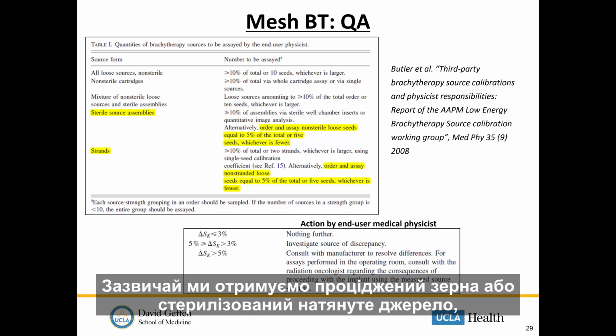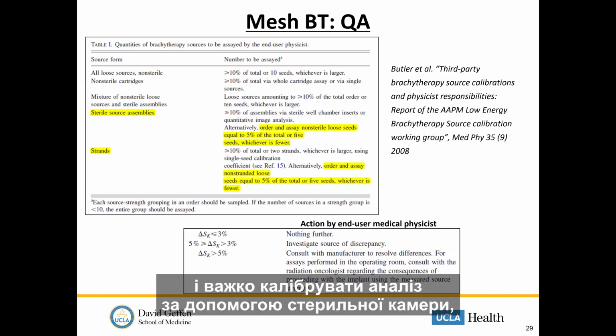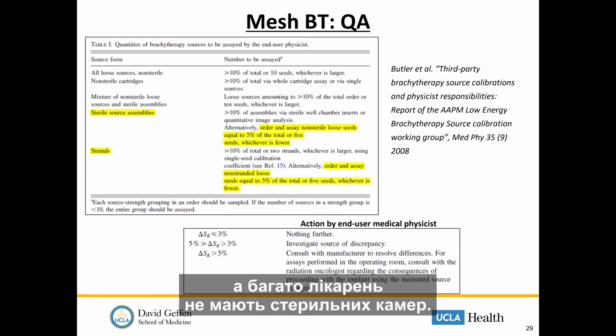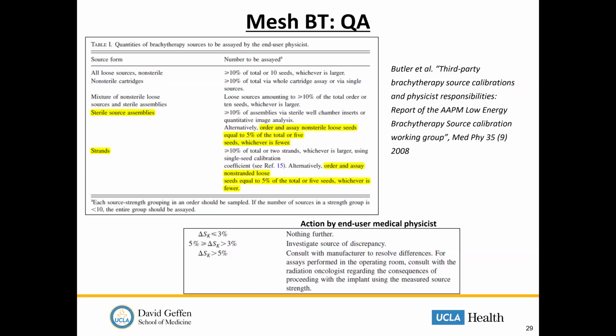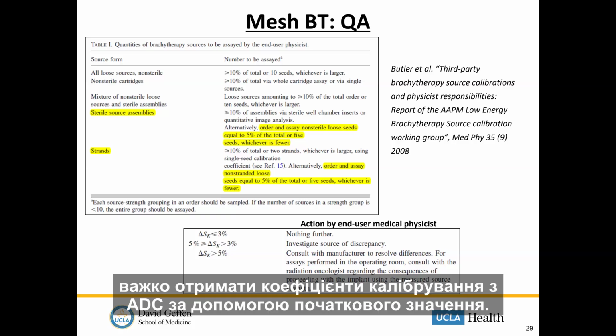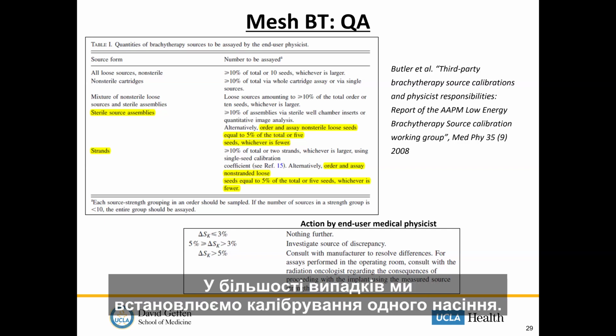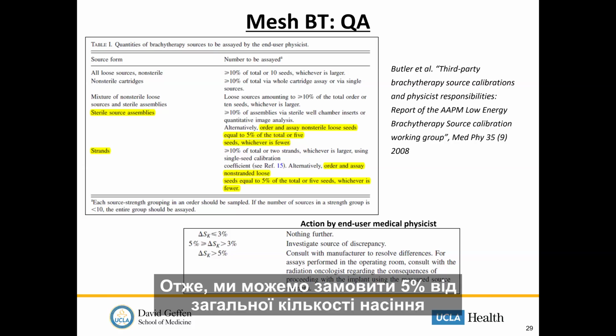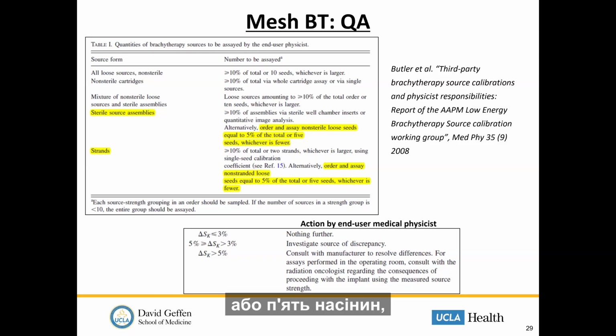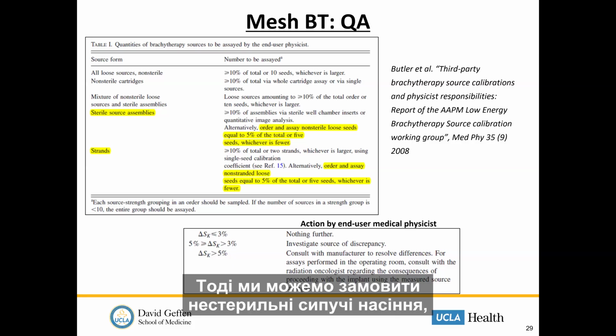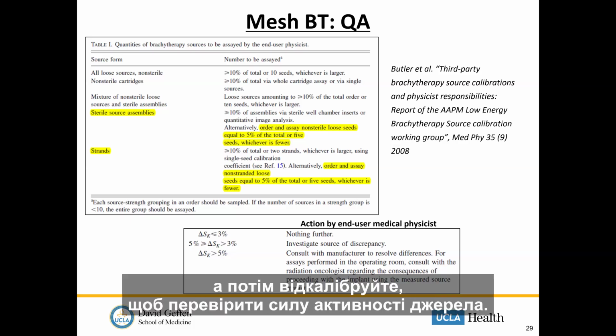Usually the strand seed, the sterilized strand source we receive, is difficult to calibrate in the assay with a sterile well chamber, and many hospital programs don't have a sterile well chamber. Also, it's difficult to get the calibration coefficient from the ADCL using the strand seed. Most of the time we rely on single seed calibration. So we can order equal to 5% of the total seeds or 5 seeds, whichever is fewer. Then we can order non-sterile loose seeds, not the strand seed, and calibrate them to verify the source activity strength.